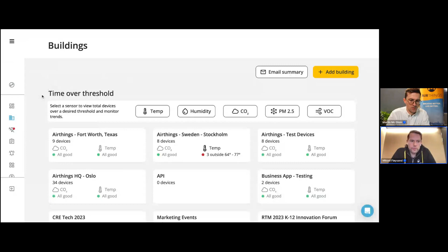The main thing to start with is just: are you ventilating too much? Are you blowing way too much fresh air into the system? We'll use the same tool for this. I'll go through it in detail since we've seen it once before. Selecting the same building, I want to do an IAQ report, but this time I'm not interested in temperature, mainly in CO2, as that's usually the proxy for ventilation efficiency. We'll look at the same month, November.